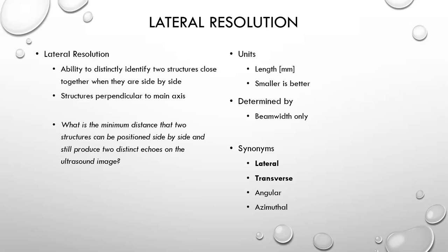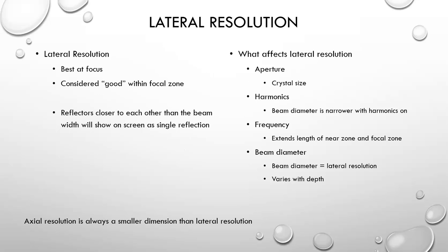Lateral resolution is best at the focus and is considered good within the focal zone. Anytime reflectors are closer to each other than the beam width, they will show up on the screen as a single reflection.